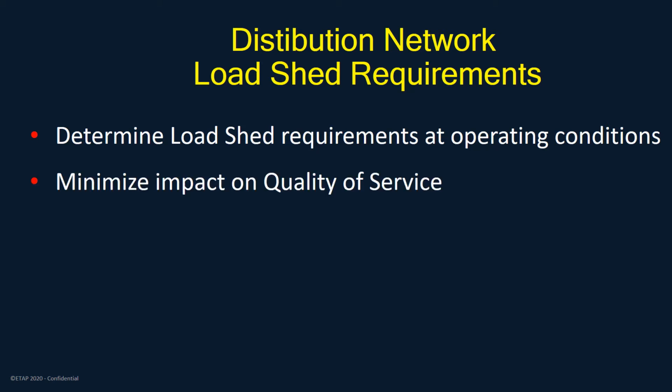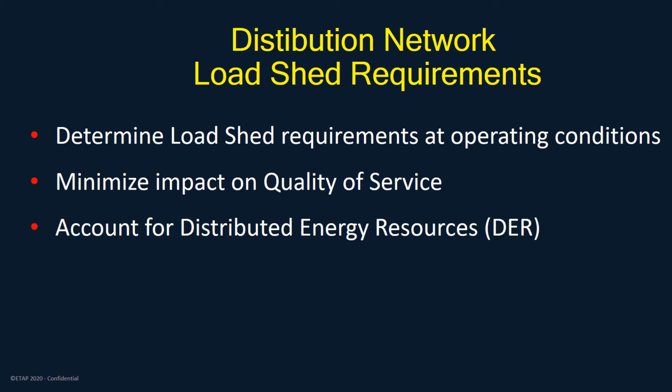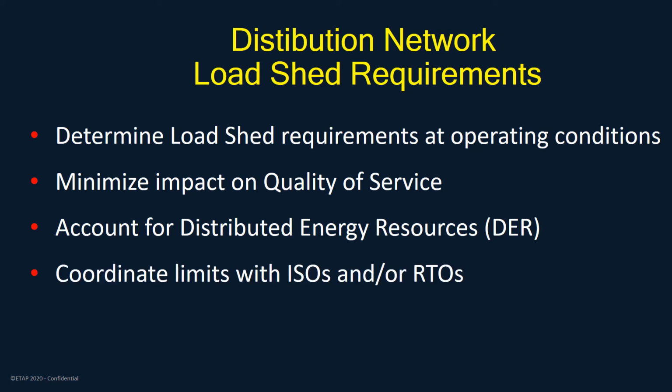Minimize impact on quality of service. As loads and feeders are being dropped, customer satisfaction drops. The system must be smart to minimize the impact. Account for distributed energy resources, DER. Determining loads to drop must account for DERs as it will influence voltage support.